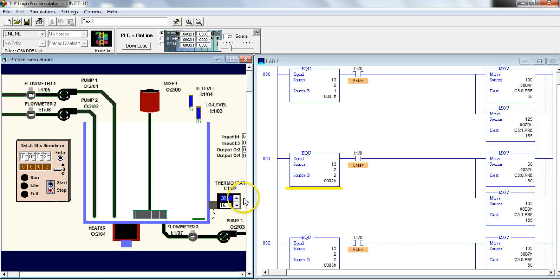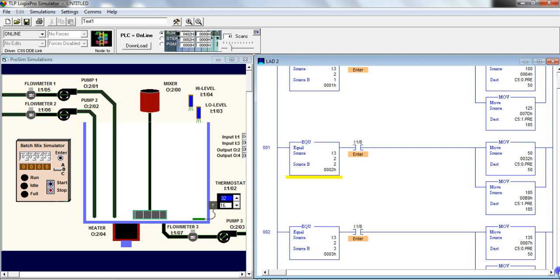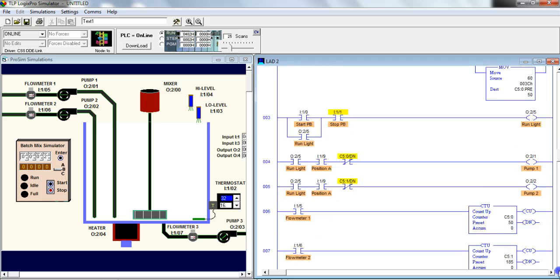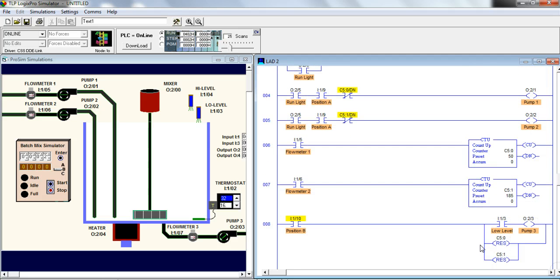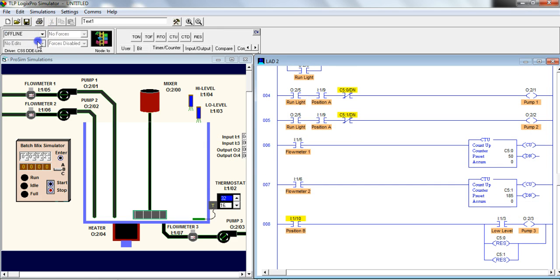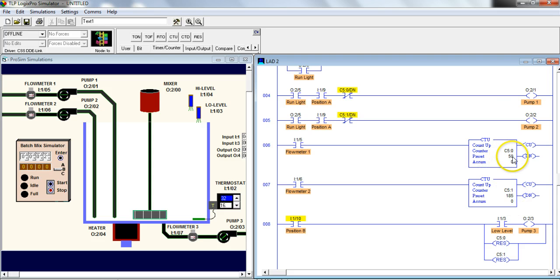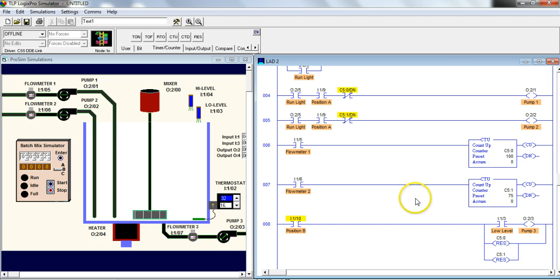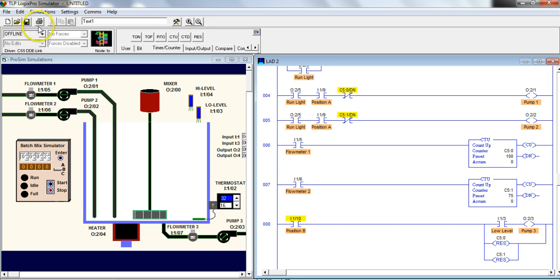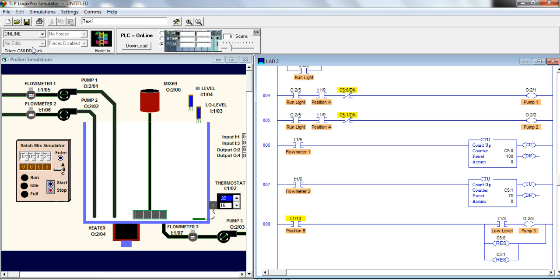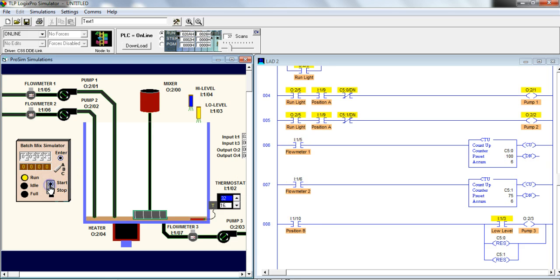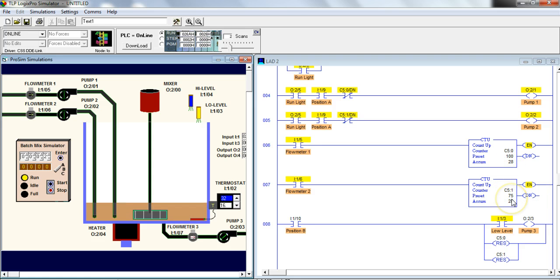Now I'm going to show you one very important thing about this. These move instructions, if I go offline right here. If you don't know that there's a move instruction tied to this counter, you may mistakenly go and change it right here. Okay, so you want to put 100 in here and let's say 75 into here. And now you're thinking that you're going to make a recipe of 100 and 175. Well, if I go online right now and go to run, that's exactly what will happen. They're going to go to 100 and 175 and stop.